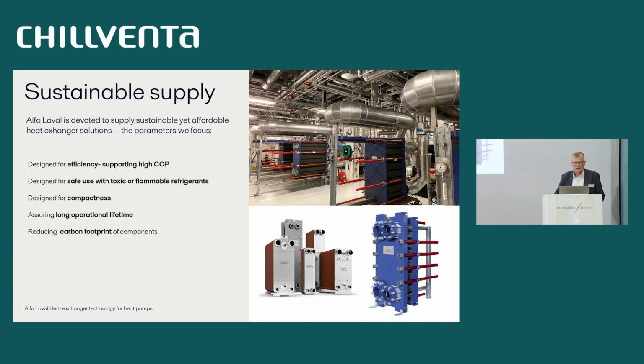Alfa Laval supplies heat exchangers, and we always want to look at sustainability. But the parameters are not only the heat exchanger itself. It is designed for efficiency, supporting the high COP; designed for safe use, with more flammable or toxic refrigerants coming, both synthetic and natural; designed for compactness; and designed to assure a long operational lifetime and to reduce the carbon footprint of the components that are included.